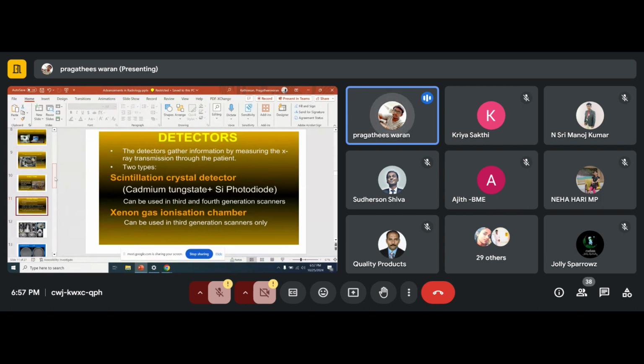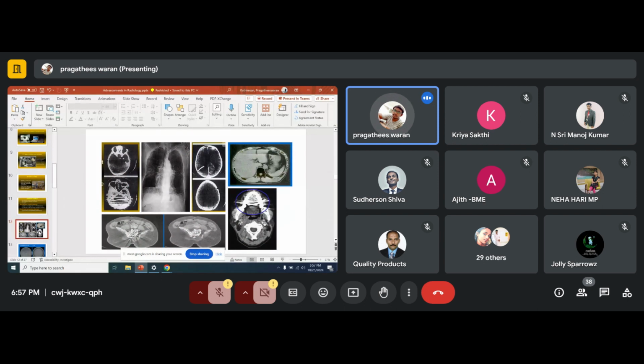So these are all the process. Next, these are all the sample images. If we see what the obstacles are while getting these images, they are artifacts. If power is not okay, if earthing is not okay, or if the patient is breathing while scanning, there are motion artifacts. This is a sample for motion artifacts. If the patient started breathing while scanning, because of this, motion artifacts will come.